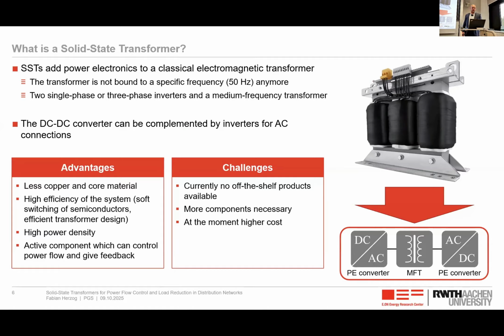The advantage is obviously we need less copper and core material, so the size shrinks a lot. We have a very high efficiency of the system because this power electronic component is very efficient, as it is soft switched. And also, for example, these isolation transformers are not very efficient compared to the large transformers. And we have a very high power density, which we will see later. The challenges here are that we currently don't have off-the-shelf products. So this AC to AC transformer is not something you can buy from every manufacturer. It's usually some very specific thing which has to be manufactured for the specific use case. Obviously, we have more components. We need the inverters, for example. And at the moment, it comes with a higher cost.